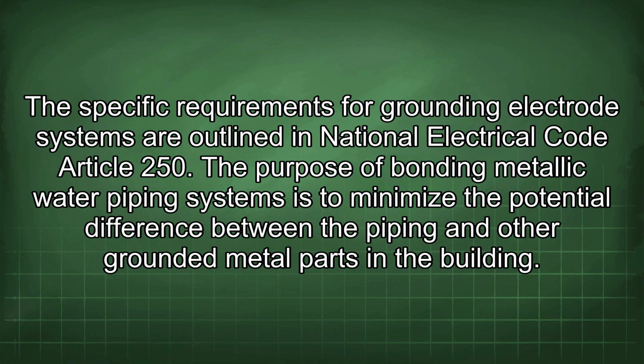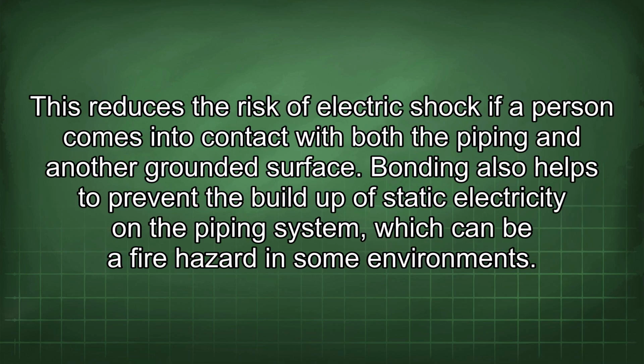The purpose of bonding metallic water piping systems is to minimize the potential difference between the piping and other grounded metal parts in the building. This reduces the risk of electric shock if a person comes into contact with both the piping and another grounded surface. Bonding also helps to prevent the build-up of static electricity on the piping system, which can be a fire hazard in some environments.